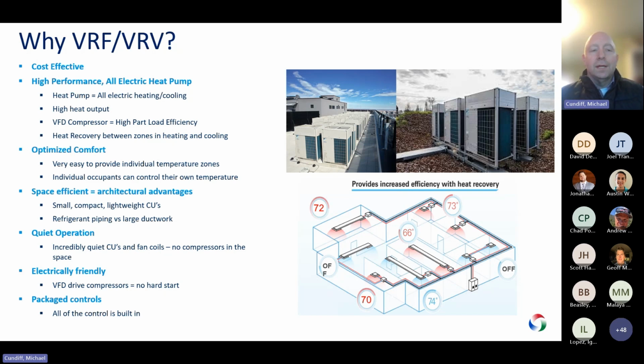Optimized comfort - everybody gets a thermostat that really wants one, so they're very easy to zone out. They're space efficient, with a lot of architectural advantages for both new construction and retrofit projects. Quiet - you don't have compressors in the space, the condensing units are very quiet, so these systems are inherently quiet by how they're designed. Electrically friendly - you do not have locked rotor amps or any of that kind of stuff on the outdoor unit, so for retrofit and new construction, even from an electrical standpoint, they're very friendly.